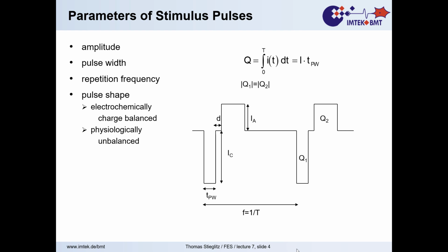Say you as an engineer and a person from the medical application, you're agreeing on certain parameters, then it's always good to draw the thing on a piece of paper or on your iPad or whatever, and ask them, do we understand the same? So amplitude, do you really mean that voltage or current going in one direction? That's your amplitude, right? And here it's the cathodic phase first.